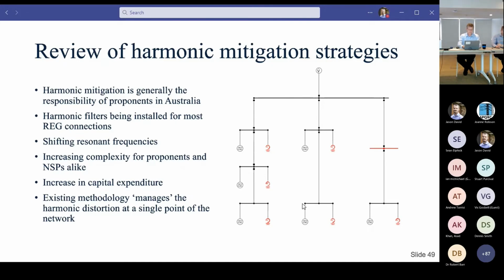To put it in example form, for a network like we've got here, we will reach the planning levels at a particular point, and provided that we reach them at that point, we can safely assume that levels across the network are all falling below the planning levels. In this example, we have a couple of long feeders, long enough for charging line capacitance to have an impact. So we can have points in the network where harmonic impedance is highest that are not at the very end of the individual feeder. That is all due to RLC components interacting and creating resonances within the network. Those are the points at which you're expected to reach your planning levels first.